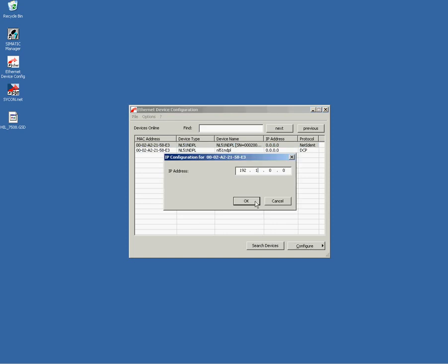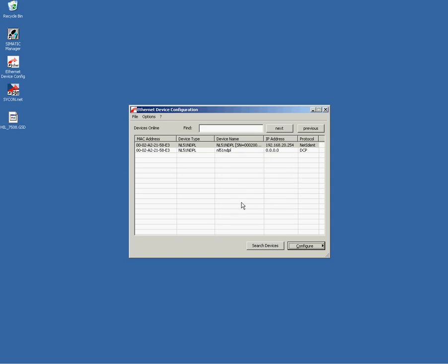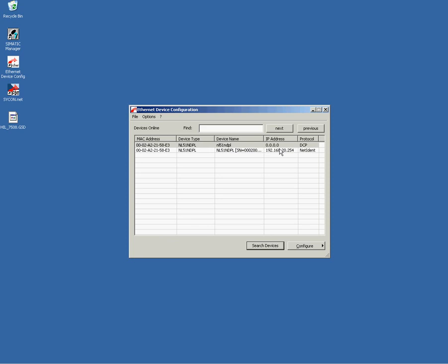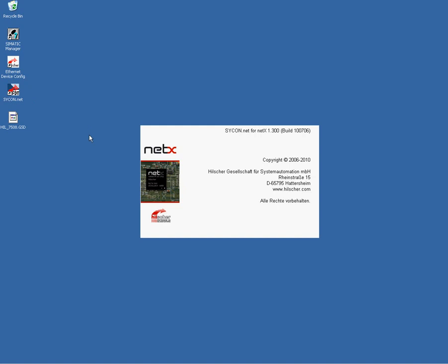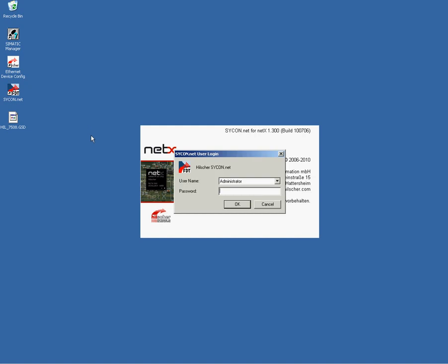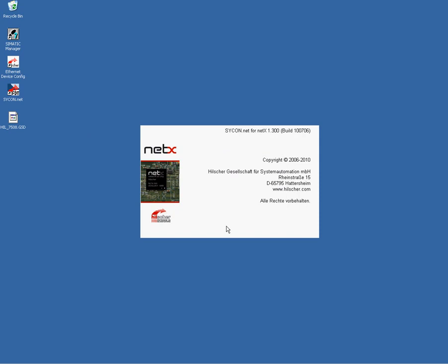When you click into the row NetIdent protocol with the right mouse button and say configure, you can now set up the Netlink proxy's IP address. Since Netlink by default has an IP address of zero. Look, when I make a rescan, my Netlink now has the IP address of my choice. So first commissioning step is now accomplished. My Netlink proxy has now a temporary IP address.